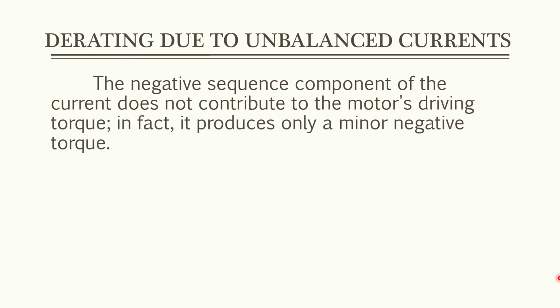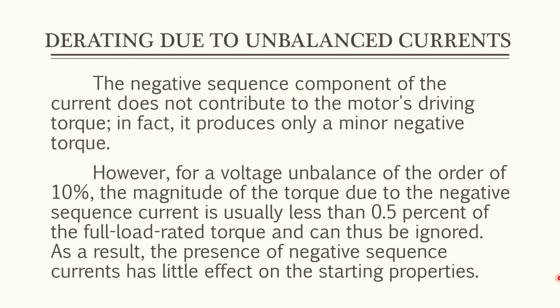The negative sequence component of the current does not contribute to the motor's driving torque. In fact, it produces only a minor negative torque. However, for a voltage imbalance of the order of 10%, the magnitude of the torque due to the negative sequence current is usually less than 0.5% of the full load rated torque and can thus be ignored. As a result, the presence of negative sequence currents has little effect on the starting properties.